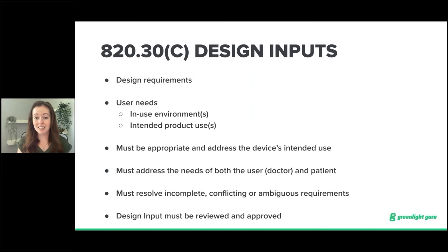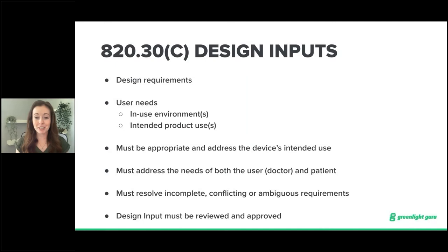The environment in which the product is intended to be used should also be properly characterized — whether it will be used in a laboratory, a home, an ambulance, or in extreme temperature conditions, for example. Design inputs are truly what's going to set you up for success moving forward by identifying verification activities early on. They encompass user needs and are going to be the baseline for your product.